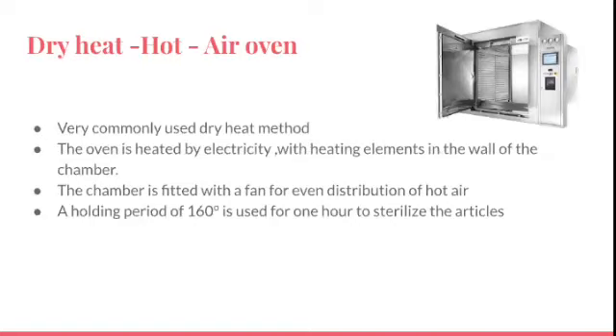The hot air oven is a commonly used dry heat method. The oven is heated by electricity via heating elements in the chamber walls, and a fan circulates the hot air evenly. The holding period is 160°C for one hour to sterilize articles placed inside.